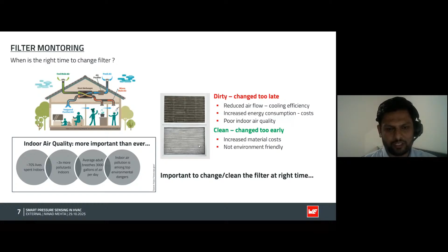As mentioned, by putting a differential pressure sensor across the filter, we can have a very accurate filter monitoring system. As the filter is being clogged, the pressure drop increases with time. In normal behavior there is a more or less linear pressure drop as the filter clogs, but at some point there is an exponential increase in the pressure drop between port A and port B, and that's where we can send an alert to the technician that it's now time to change the filter, because based on the pressure drop information, we can predict that maybe in 4 weeks there is a high chance that the filter gets completely blocked.